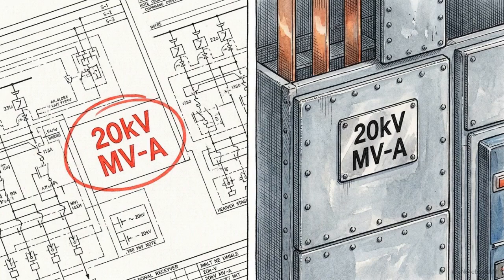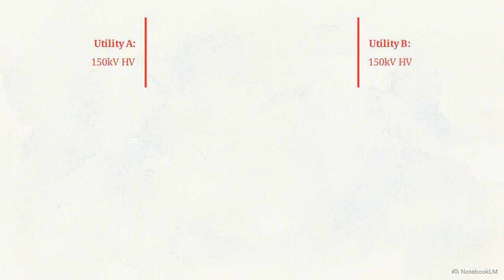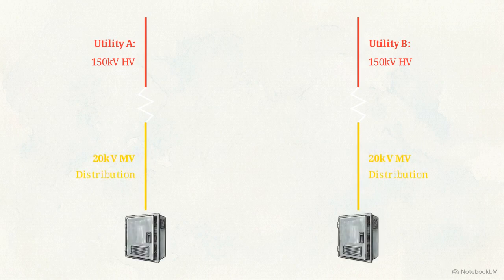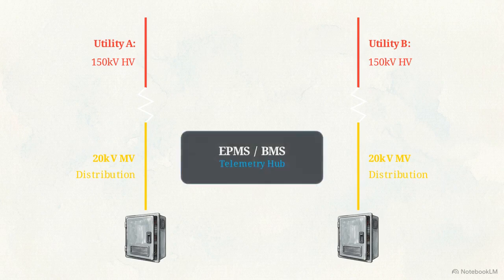Standardized nomenclature prevents catastrophic switching errors by ensuring every operator identifies the same voltage class on every drawing and permit. In this AB critical power path, the 150 kilovolt incoming utility lines are classified as high voltage, or HV. The 20 kilovolt switchgear and distribution lines are classified separately as medium voltage, or MV. Mixing these naming conventions invalidates safety permits and isolation criteria. Full acceptance requires proving both the physical power delivery and secondary telemetry. The raw current and EPMS data must be validated as distinct concurrent evidence chains.